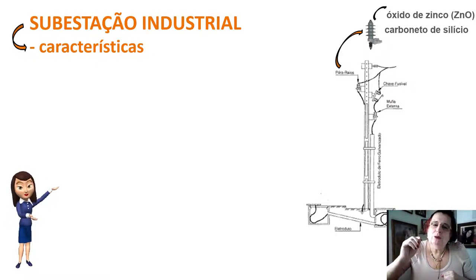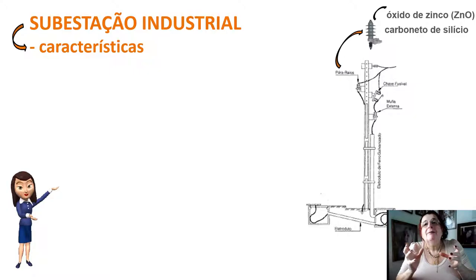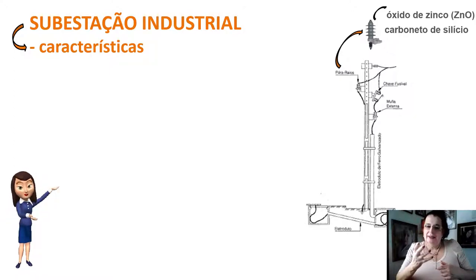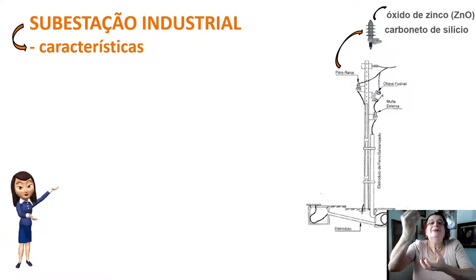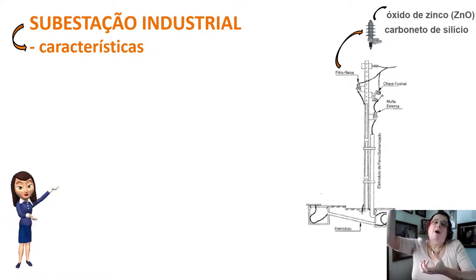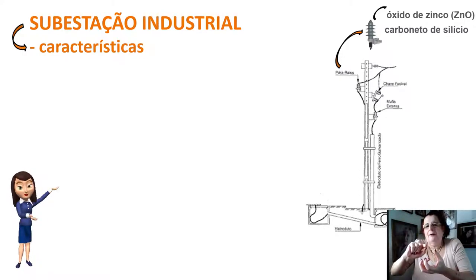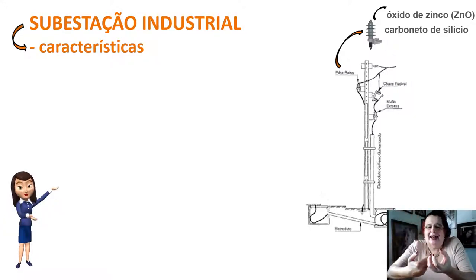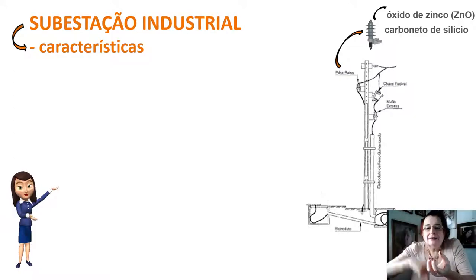Quando temos uma linha de transmissão elétrica de alta tensão, ela recebe raios em ambiente atmosférico propício. O para-raio, ao receber o raio de alta voltagem, drena essa alta voltagem para a terra, pois está ligado a uma barra aterrada. O raio cai na rede de distribuição de 13 mil volts, gera elevada tensão, e o para-raio percebe que a tensão está muito acima e drena essa tensão ao terra.